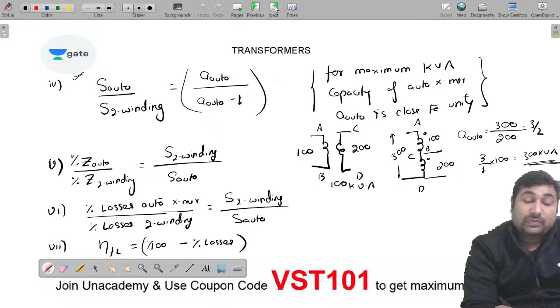If we have a two winding transformer designed for a certain fault level and just by connecting the two winding transformer as an auto transformer, then the fault level increases to a much higher value. For that the protection is not designed. That is why we never connect a two winding transformer as an auto transformer. Whenever we have to design an auto transformer, we always select a new, fresh transformer to design as an auto transformer, because we have to calculate this per unit short circuit current and accordingly we have to design the protective devices. Is my point clear?